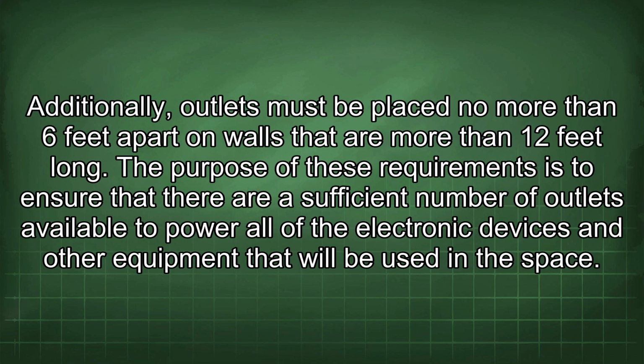Additionally, outlets must be placed no more than 6 feet apart on walls that are more than 12 feet long. The purpose of these requirements is to ensure that there are a sufficient number of outlets available to power all of the electronic devices and other equipment that will be used in the space.